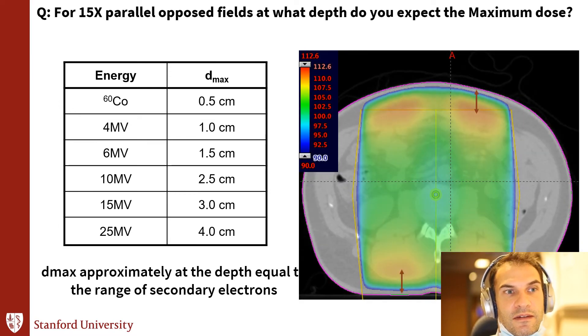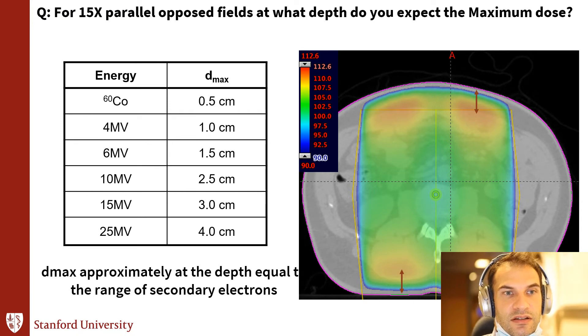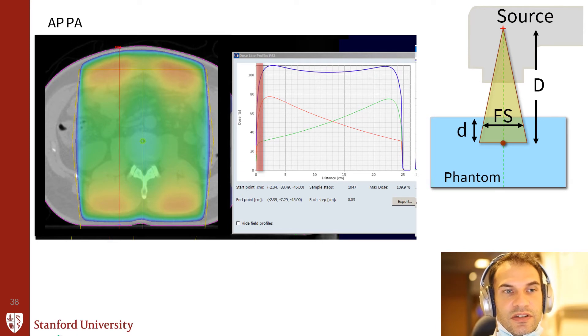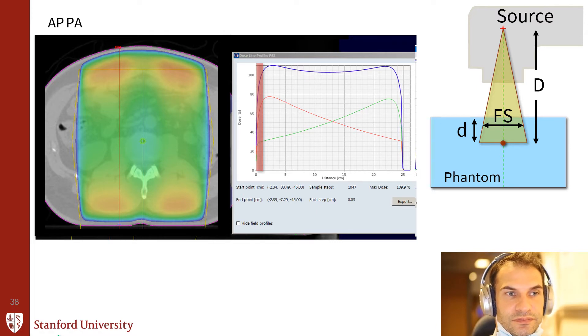Here's a question: for 15x parallel opposed fields, at what depth do you expect to see the maximum dose? Here is a picture of parallel opposed radiation fields — you see there's higher dose near the edges and lower dose in the middle. From the table, the answer is about 3 cm for 15x. Even though there are two beams, they don't really change the shape of the PDD curve. Each anterior-posterior beam is one PDD curve and the posterior-to-anterior beam is another. When they add up, you still get maxima around the same position as in the individual beams. The physics between the water tank and the patient is still approximately the same.